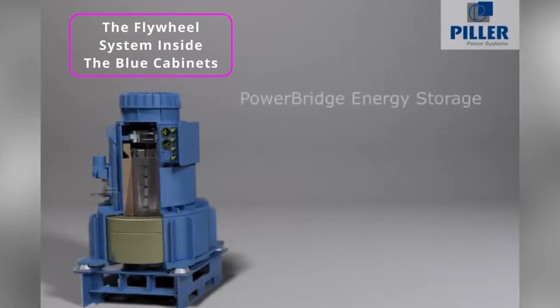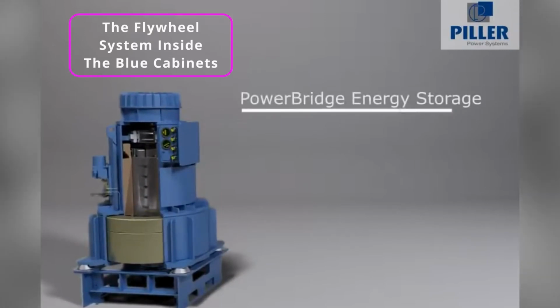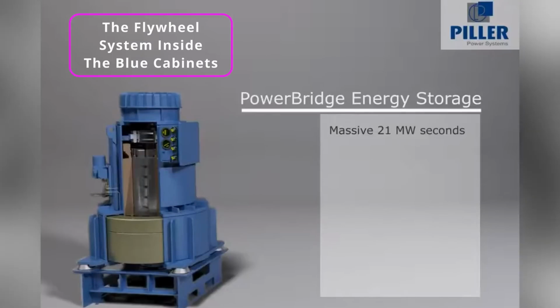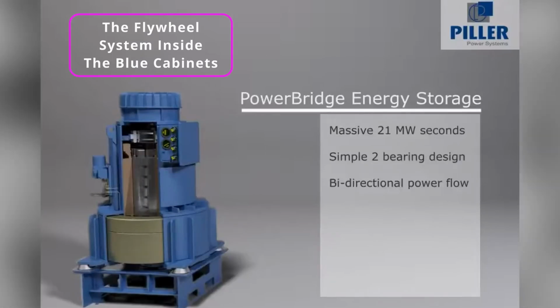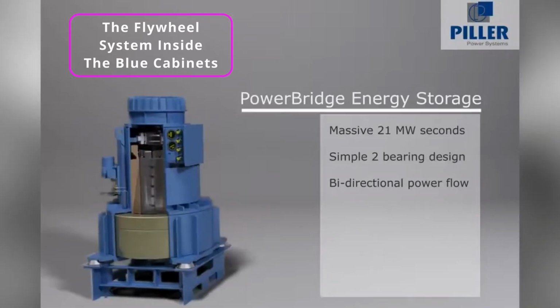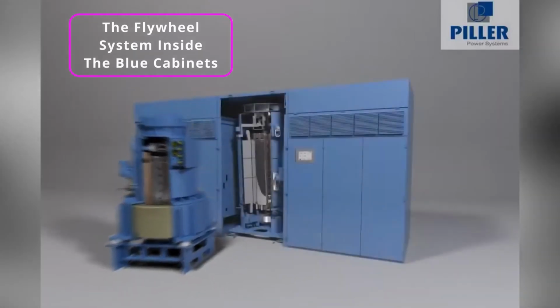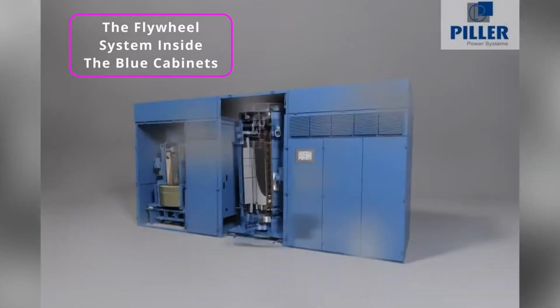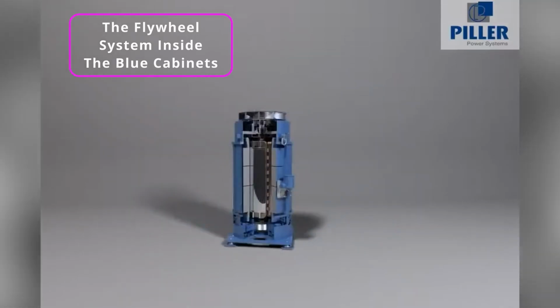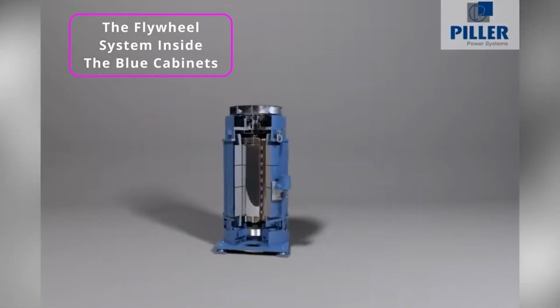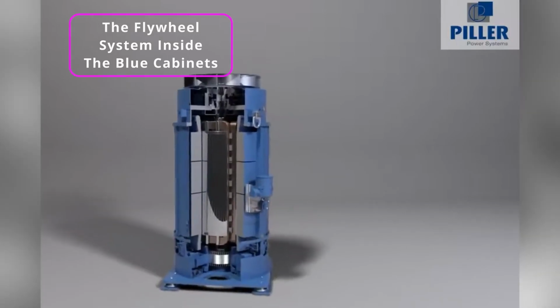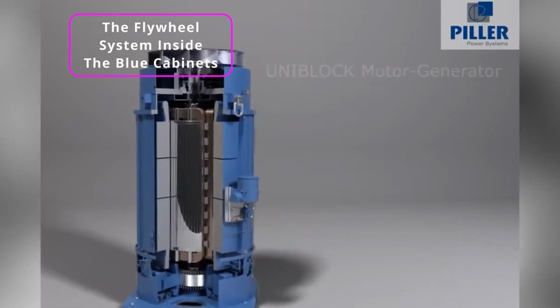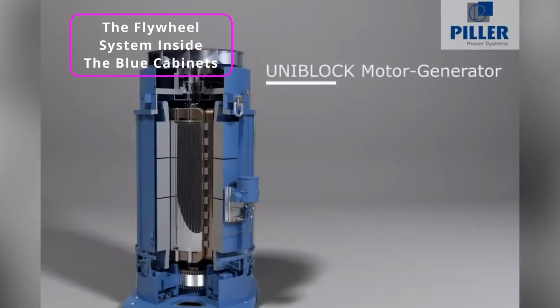It can range from about 250 kilowatts up to about 1.3 megawatts in size. Okay. And what happens is there's a large rotating drum inside there that's spinning, magnetically levitated so that it has very little friction in a hermetically sealed container. When the power goes out, the resistance of the motor windings slows that container down as it's generating power, and it slowly spins down. When the generators kick on and everything's hunky-dory, those same motor windings are now a motor and will spin it back up and get it going.